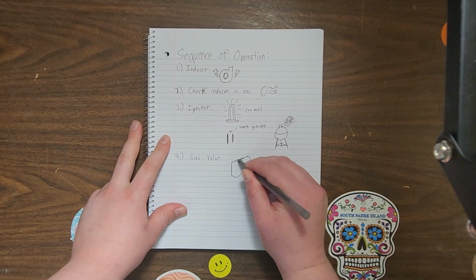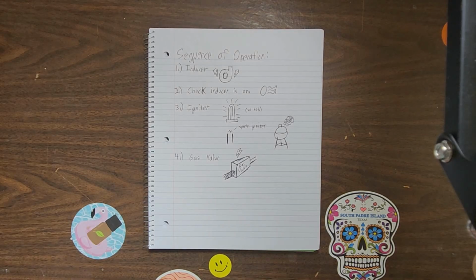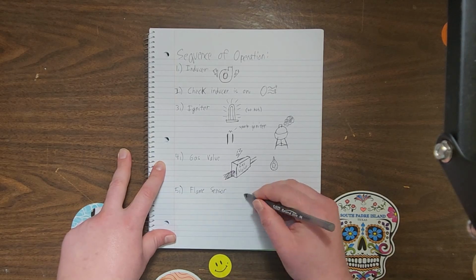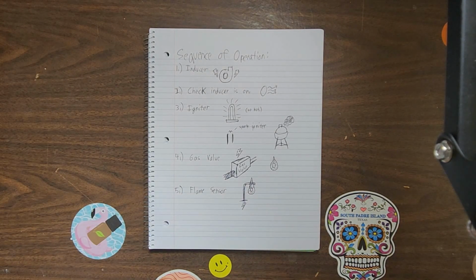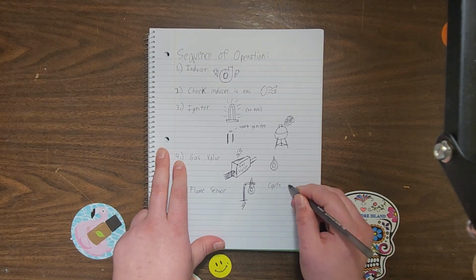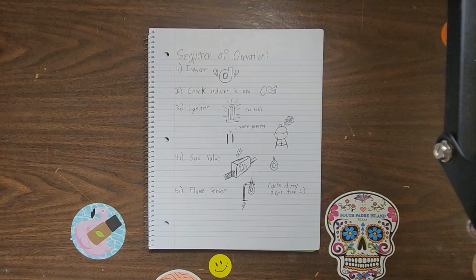Next, the gas valve will open. This will start the flow of gas, and the igniter will also ignite the fuel. As long as the gas valve is open, the furnace will continue to operate. And the only way it will do so is by passing a few safety checks, including the flame sensor. This will detect a flame by generating a small voltage that goes back to the furnace control board. As long as there is sufficient voltage generated, the gas valve will stay open. If the flame sensor doesn't detect any flame, however, or the sensor is so dirty that it cannot generate any voltage, it'll shut off the gas valve.